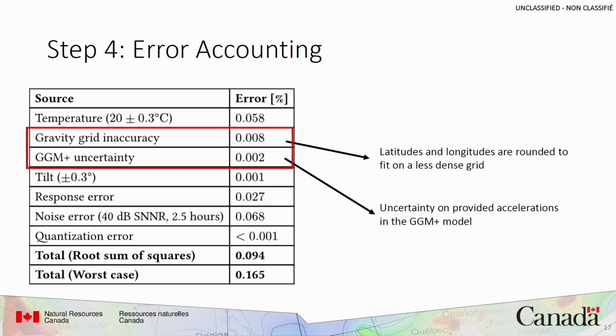At the Canadian Hazards Information Service, the pressure is really on the field installation engineers, and if we're doing this opportunistically because, say, they're changing a cell modem at the site, they're not going to want to spend more than a few hours at the site. So this is the question: what's the ambient noise level at the particular site, and how long do we actually have to deploy a side-by-side test there? So that's really the controlling number in the error budget once we deal with temperature and local gravity. Advance, please.